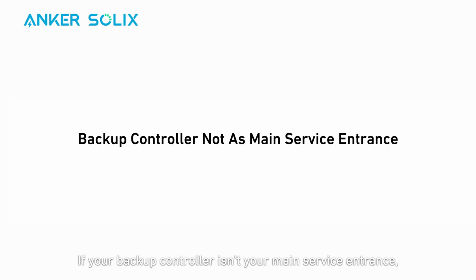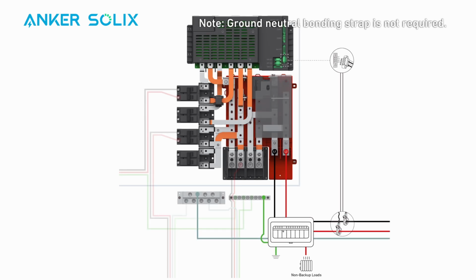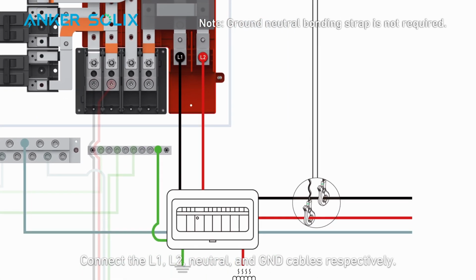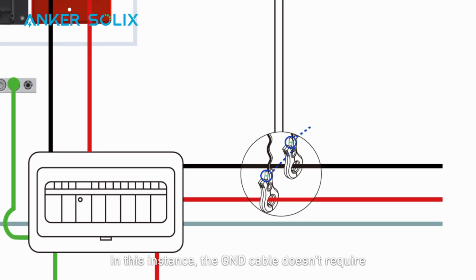If your backup controller isn't your main service entrance, the main breaker is inside of the main panel. We need to connect the backup controller to the main panel first, and then go through the power meter to the grid. Connect the L1, L2, neutral, and ground cables respectively. In this instance, the ground cable doesn't require a ground-neutral bonding strap.